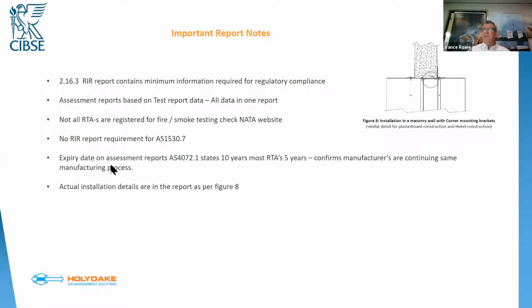Not all RTAs are registered for particularly smoke testing. I would advise people when they're looking at reports, particularly from obscure places, that they check the NATA website. As I said to you before, I've seen reports put out there as evidence of compliance, particularly for smoke dampers recently. And then when you actually look at the testing authority that did it, they weren't certified to perform the test. There's actually no RIR requirement for AS 1530.7, so that's the smoke damper testing standard. So that does make it really difficult for industry, because there's no requirement to record a pass or a fail in AS 1530.7. That requirement is listed in the performance requirements that sit in AS 1682.1, and in particular, you really want to be looking at table 2.4.